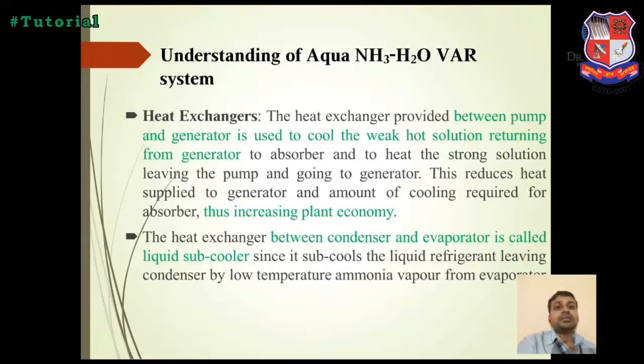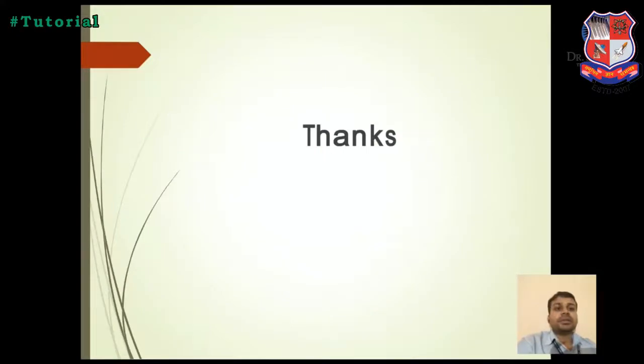There are two heat exchangers used in our VAR NH3-H2O cycle. The first is between the pump and generator; it cools the weak solution and heats the strong solution leaving the pump and going to the generator. This reduces the heat supplied to the generator and the cooling required for the absorber, thus increasing the plant economy. The heat exchanger between the condenser and evaporator is called a liquid subcooler, since it subcools the liquid leaving the condenser using the low temperature ammonia vapor from the evaporator. This gives a higher cooling effect for the same work input from the generator. Okay, thank you.